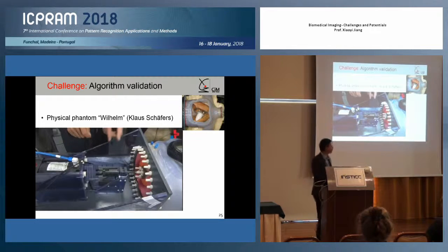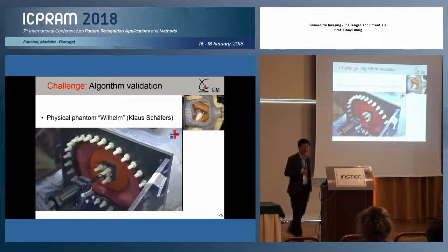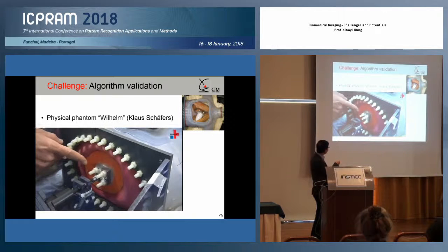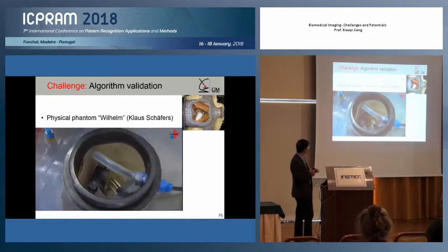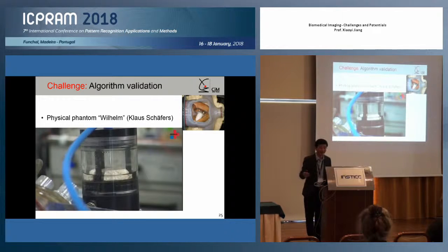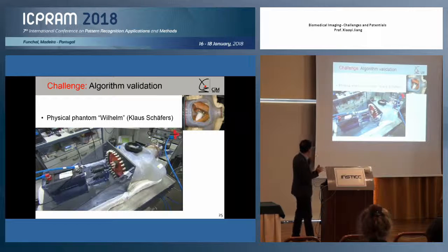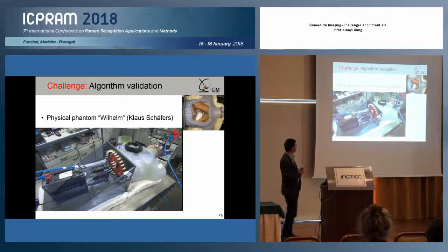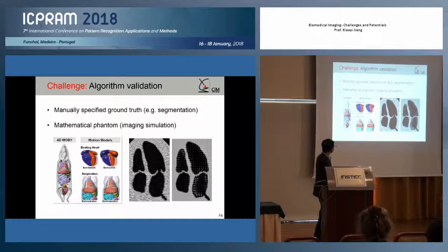This is my colleague Klaus Schäfer. He has built a so-called phantom. It's a hardware body with all the organs, which are controlled physically, and all the parameters of the organ movement are controlled by software. So everything is under control in some sense. We also use this particular form of data acquisition for algorithm validation. So these are the two standard forms of validation, and this is a very specific form in medical imaging.